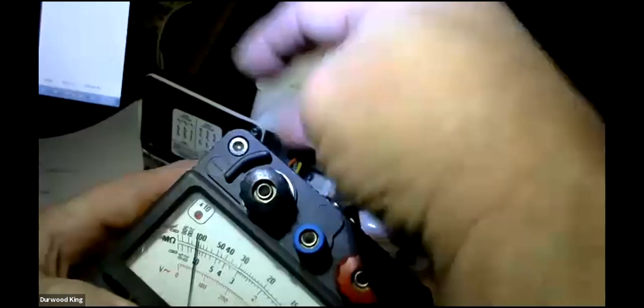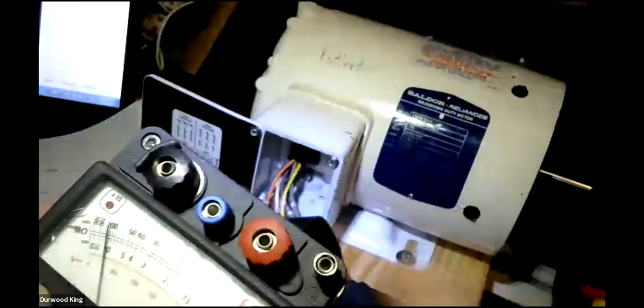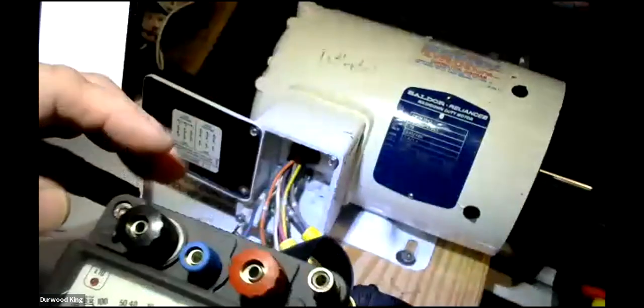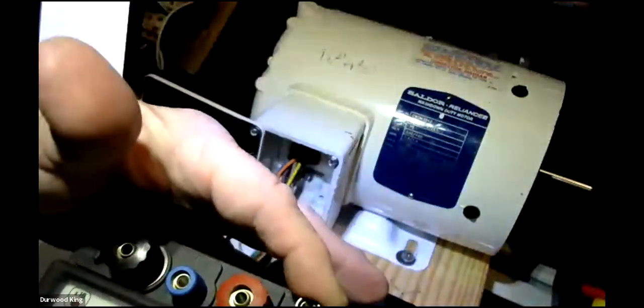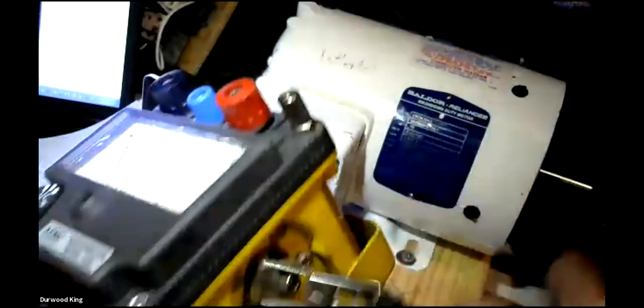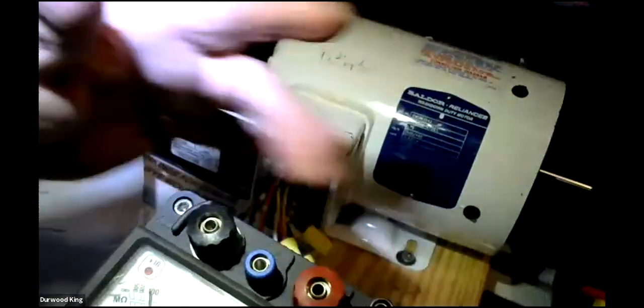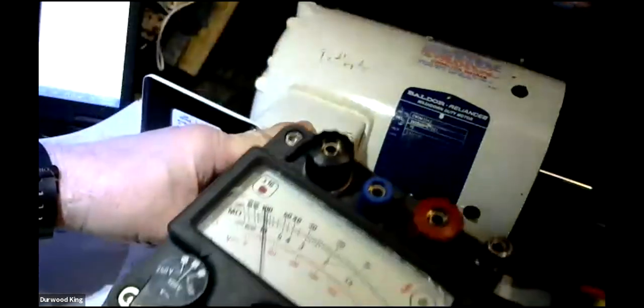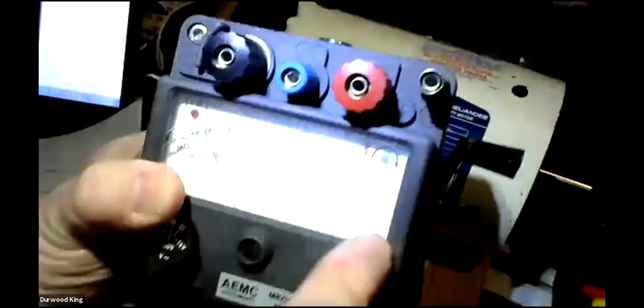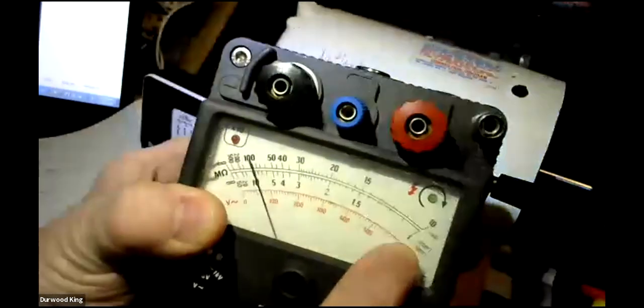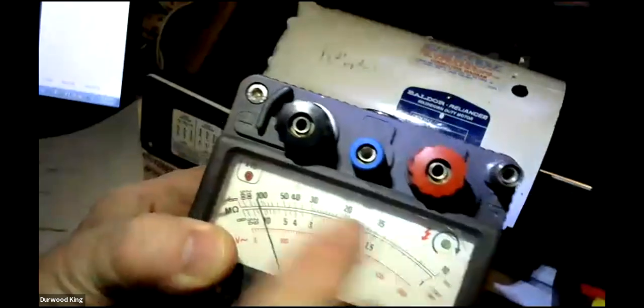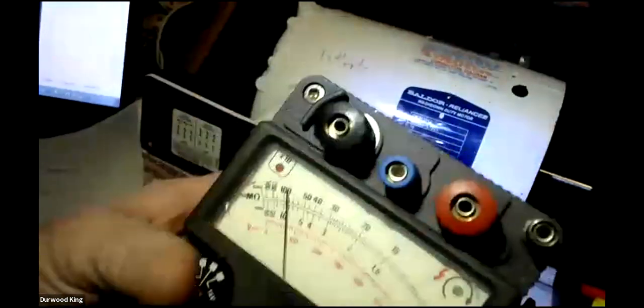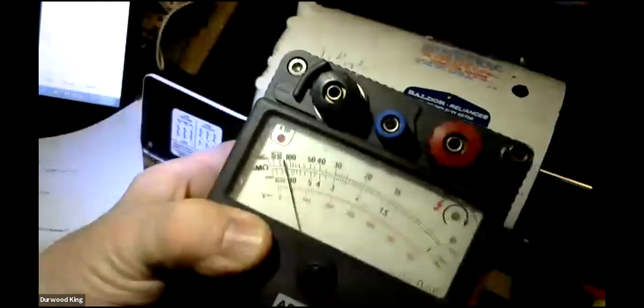Basically, these are your 2 leads. That's what you would test a motor with. You hook a lead from this to the actual ground, and that's what you're going to check. This is actually a ground for the instrument itself, so you want to ground the metal parts of this to the motor also. Then you use your ground and your hot to do the test the same way we just did a while ago. It tells you the minimum reading is 1 megohm right here. When it swings way over and pegs, it's bad. If it stays way over to the left, way up in the high megohms, then you're fine.